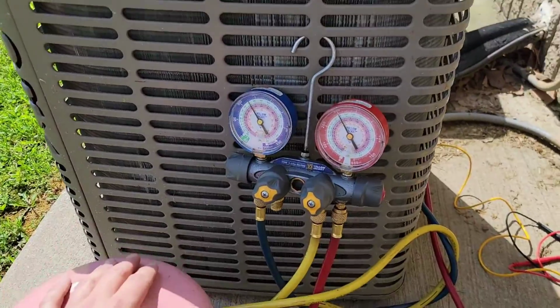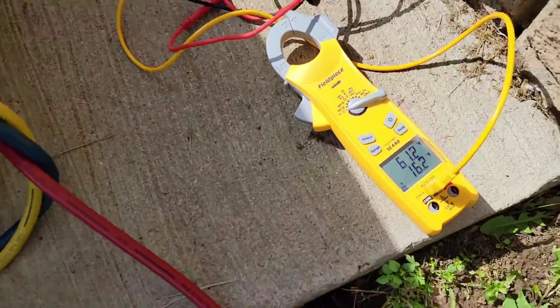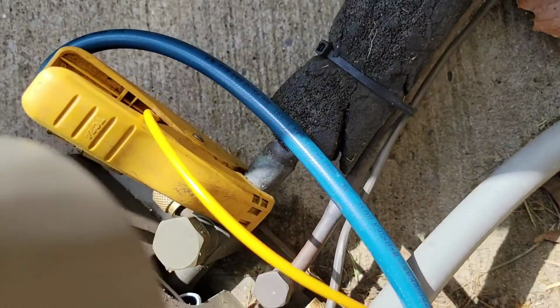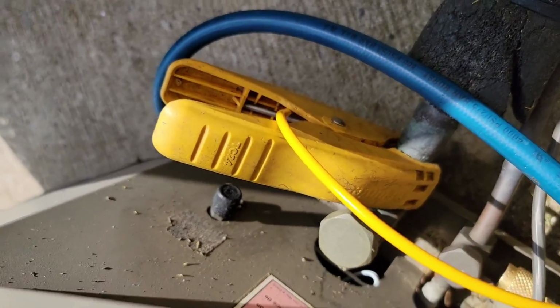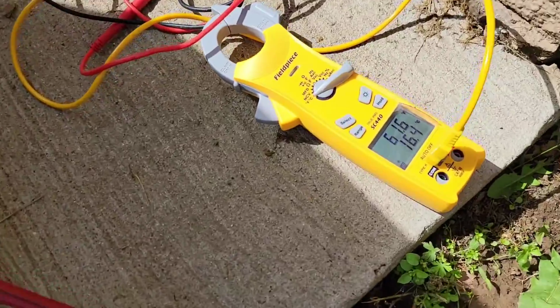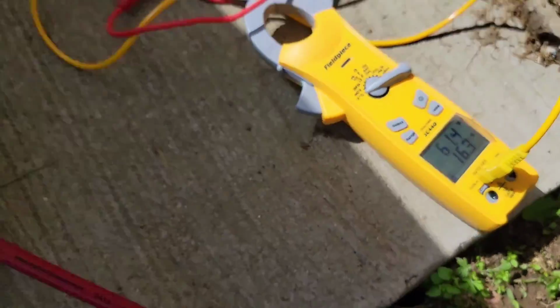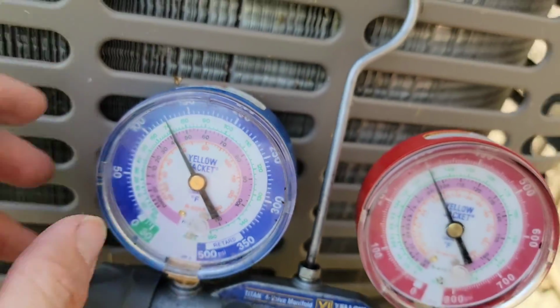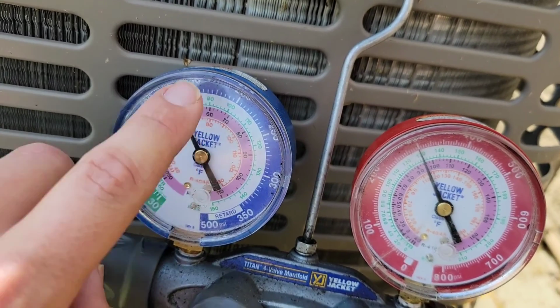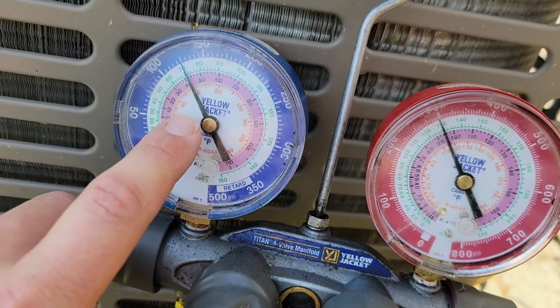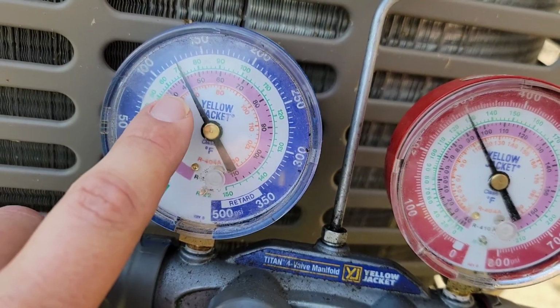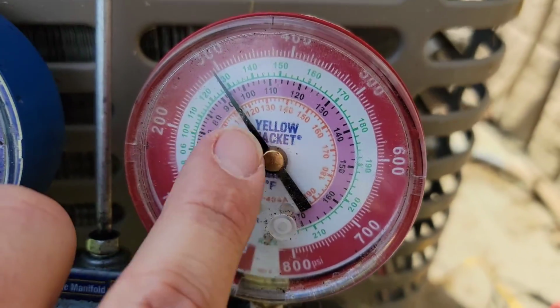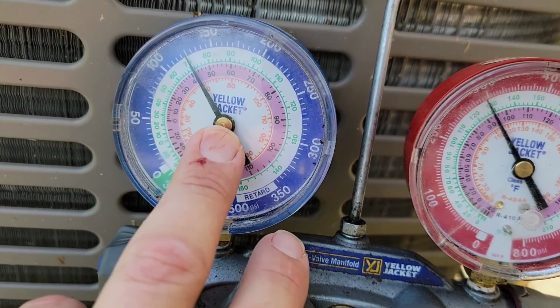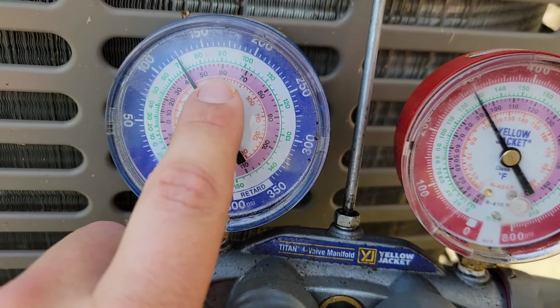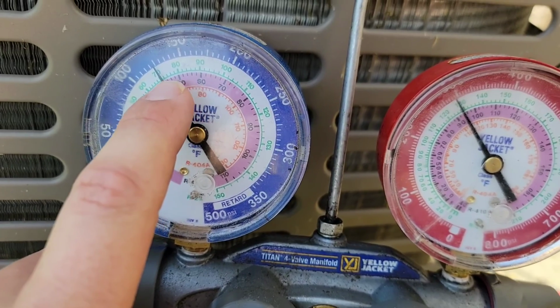All right, now charging some R410A equipment. I'm going to show you the pressures here. We got the clamp on temperature probe or thermometer on the suction line of the compressor, vapor line going into the compressor. It's 61 degrees. Same thing. We're trying to pretty much get the same saturation temperatures, except the pressures are different. Pressures are higher. Suction's 125 right now. Head pressure's 300. We're working in the server room. Right now it's 80 degrees in the server room. So I probably need to get it up here a little bit, maybe in between.